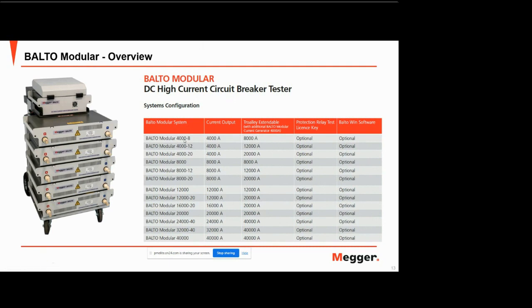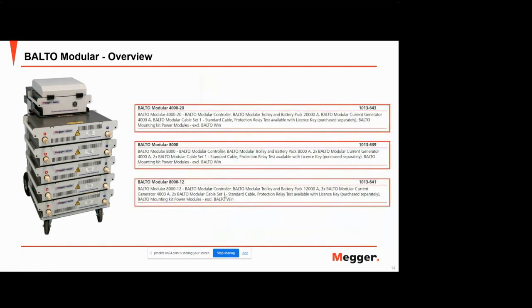So with the Balto modular, you can extend your original purchase. So if you buy a 4,000 amp system or an 8,000 amp system, depending on the trolley that you buy with that, you can then extend it for your future requirements with additional current generators. As you can see in the picture to your left, you can see where you've got up to 5 current generators. Each one of these current generators outputs 4,000 amps. So you can easily extend your Balto modular to suit your future needs. And in the data sheet, you can also see exactly what each system contains. It's very clearly stated in terms of the capability of it, but also what's included with each of the complete systems.